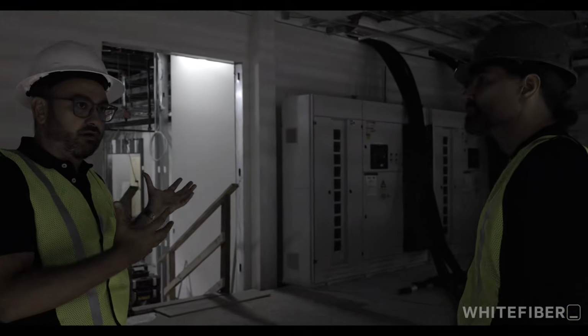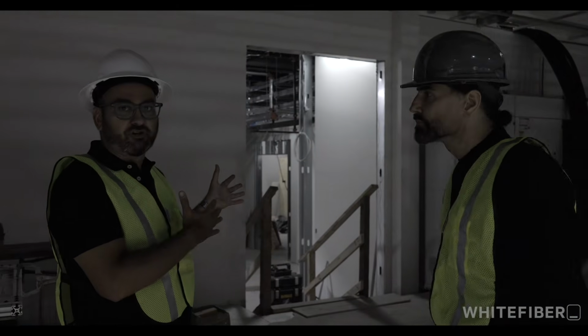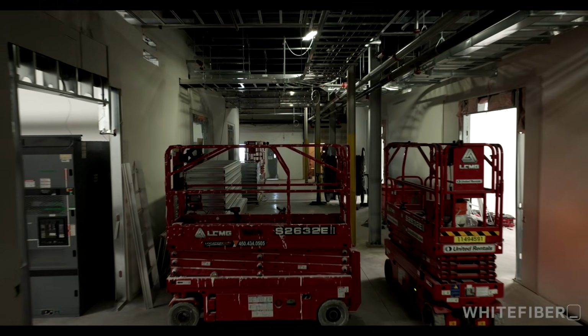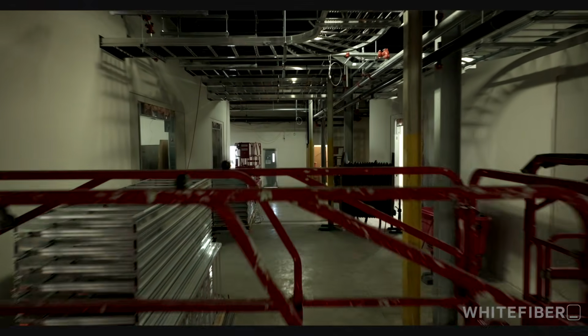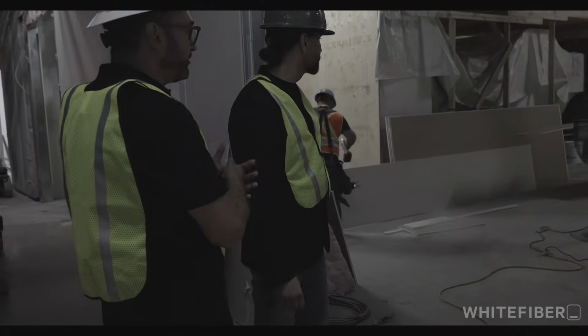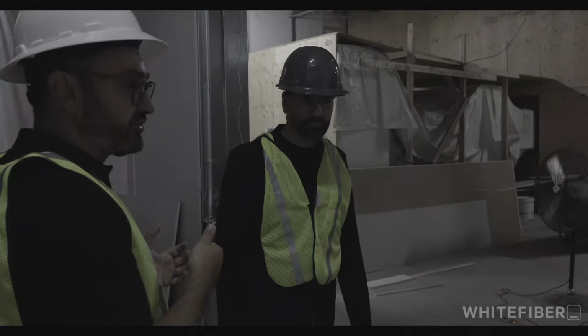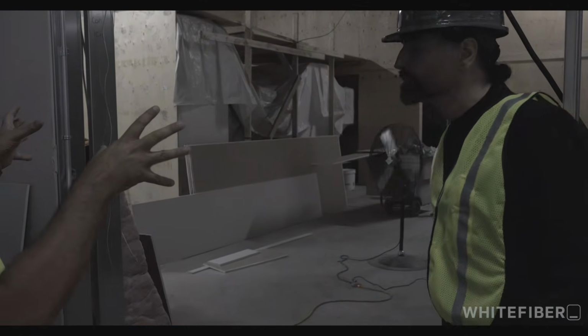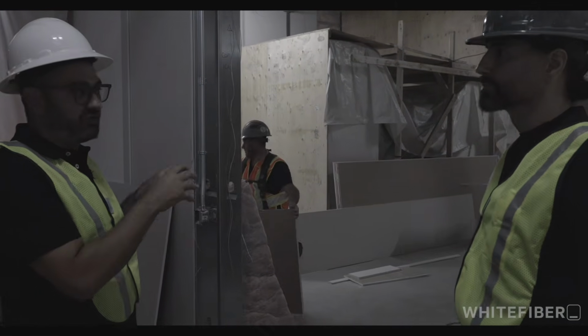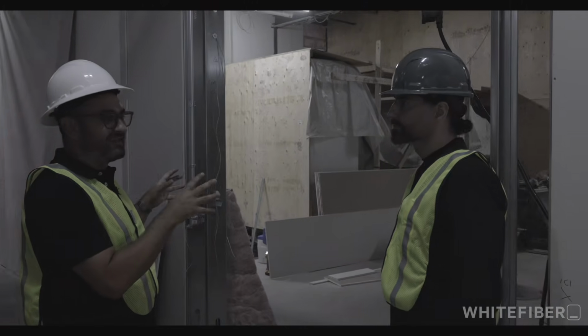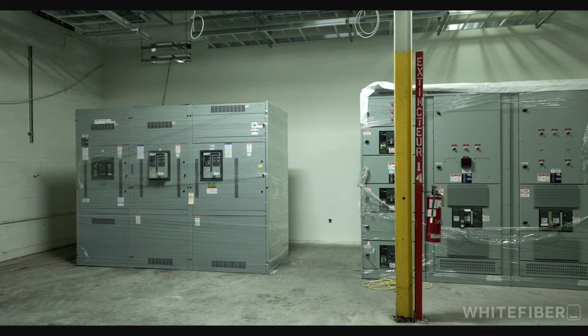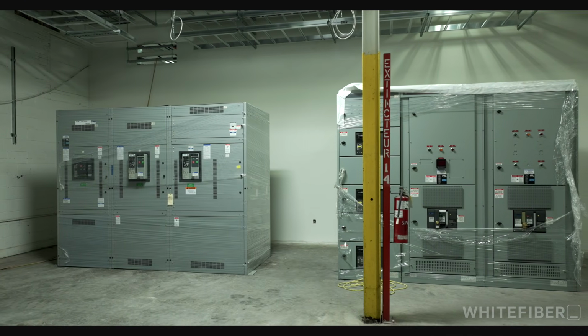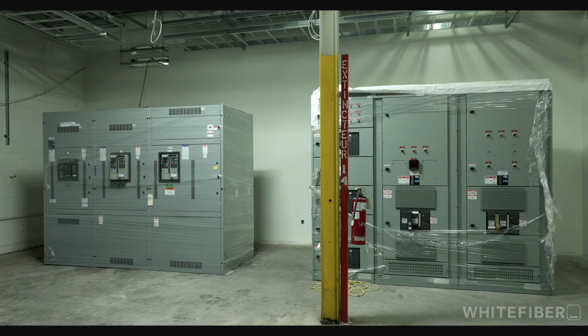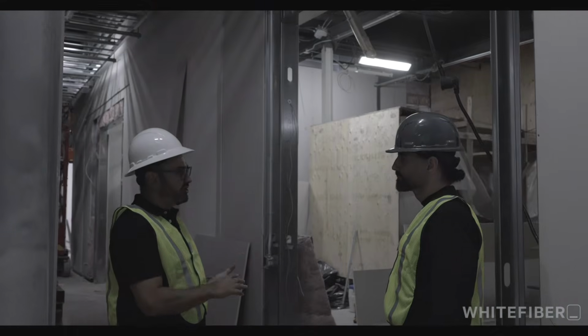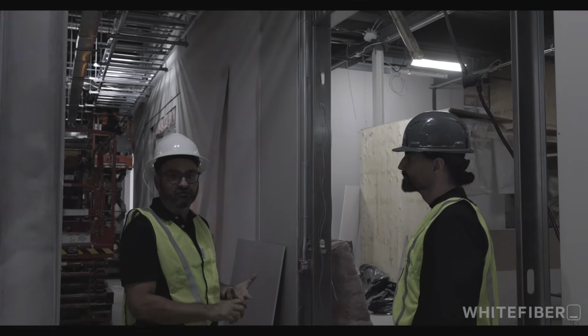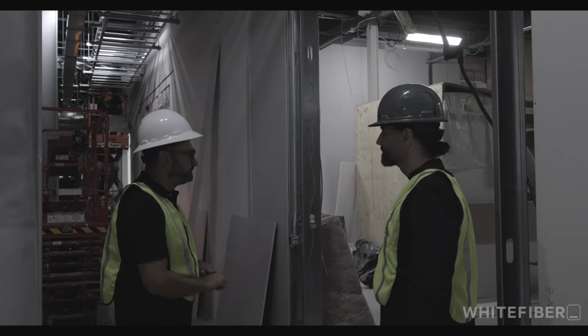We're gonna go look at the electrical infrastructure that supports all this. So as you can see, a lot of work happening. We got over 120 people on site trying to make this delivery. Here we have one of our generator rooms. So these are in place in case of an extended utility outage. We got about just over 24 hours of fuel on site to support any long-term utility outage. Contracts with fuel providers to replenish the fuel within 4 hours.